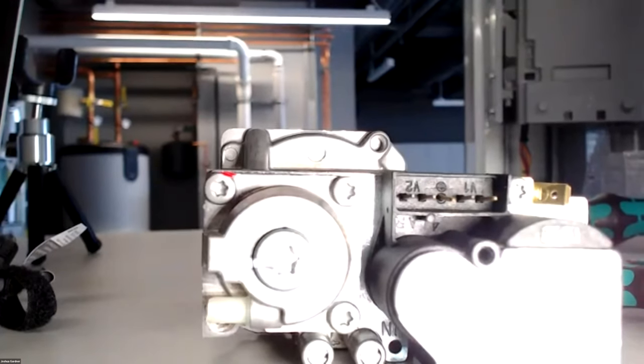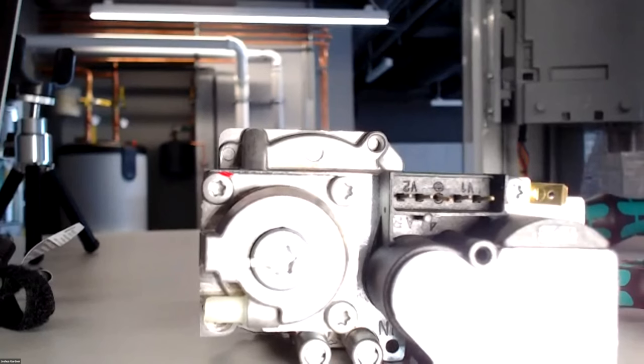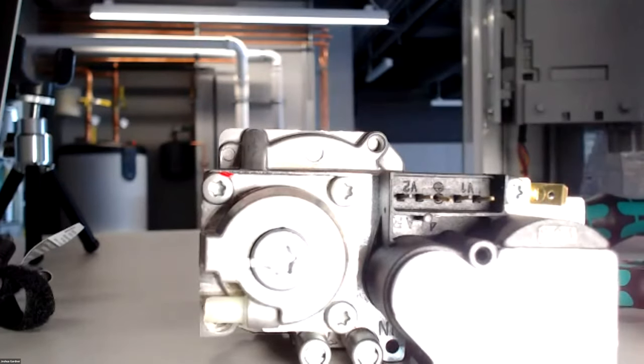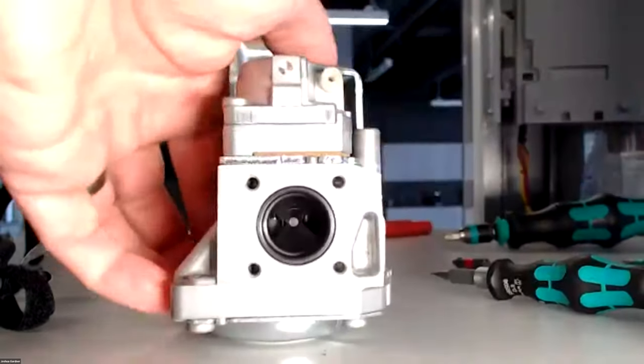Now that's all dependent on making sure you have good gas pressure. That's the first thing we need to confirm. Because if your gas pressure is way off, if we're dropping too much, then I don't want to go adjust that yet. I want to check our gas pressure, get that in check. Once that is, then we can move on. That's how we adjust that offset.